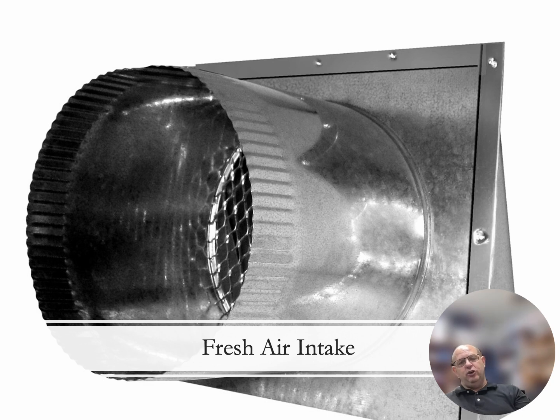A couple of things that this is going to do for us is it's going to create a positive pressure on the inside, and it's going to minimize our infiltration and our ventilation CFMs that we are going to need for that environment itself. Different types of systems will have some sort of mechanical ventilation, and this is what we're going to be doing within this system, giving us mechanical ventilation rather than having that air infiltrate through the windows, infiltrate through cracks in the wall.